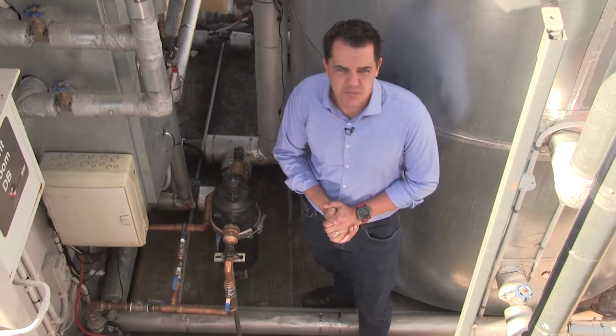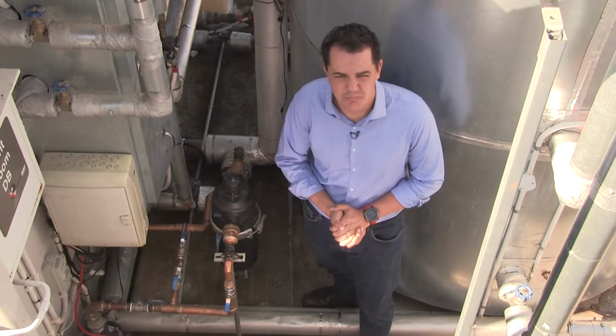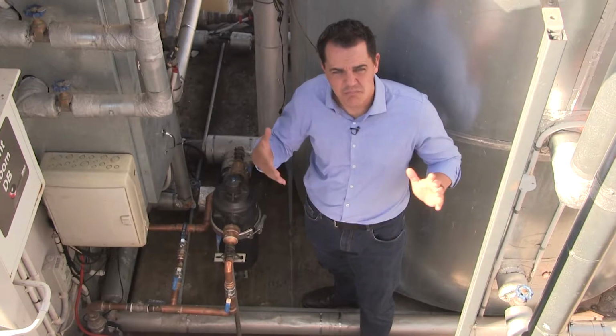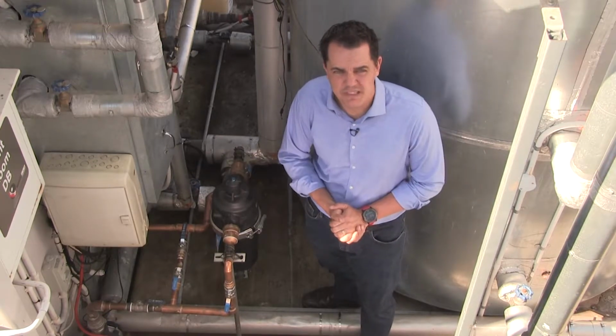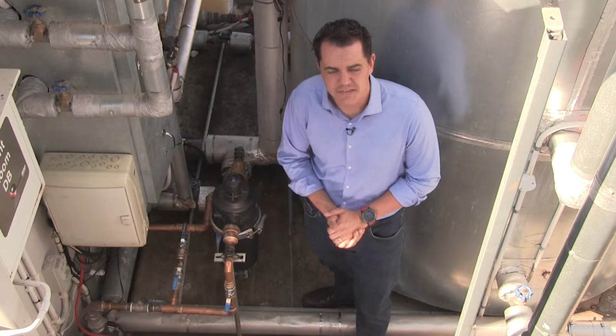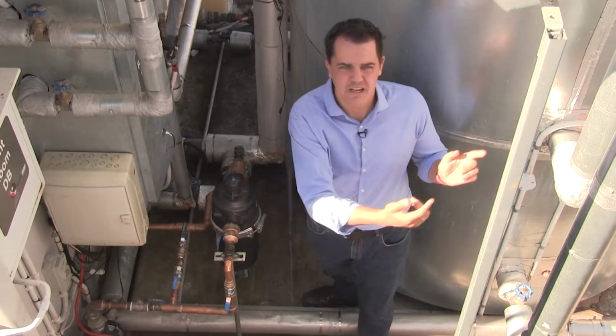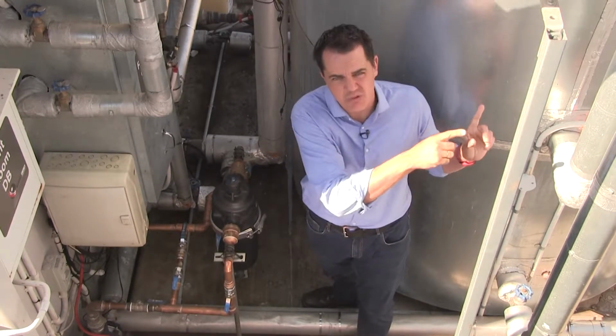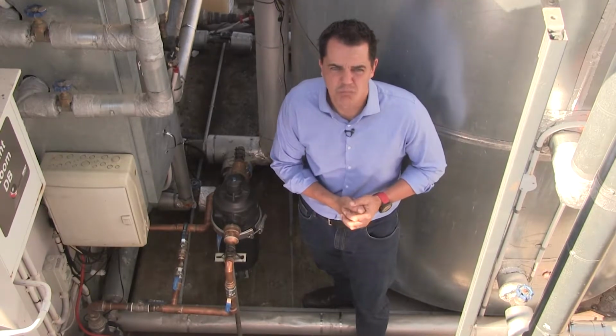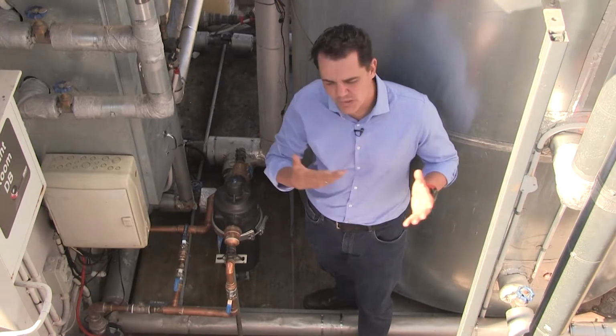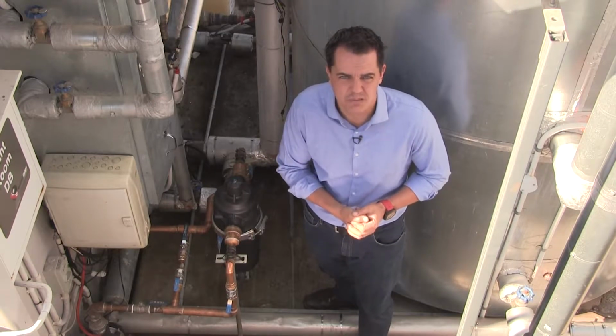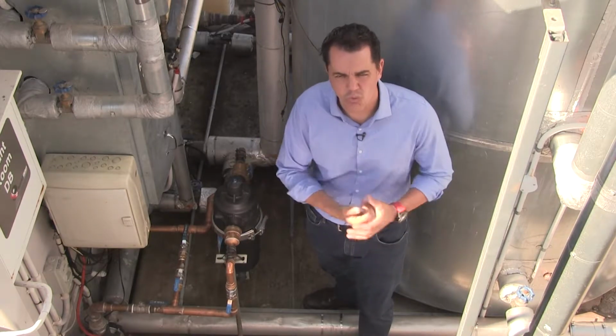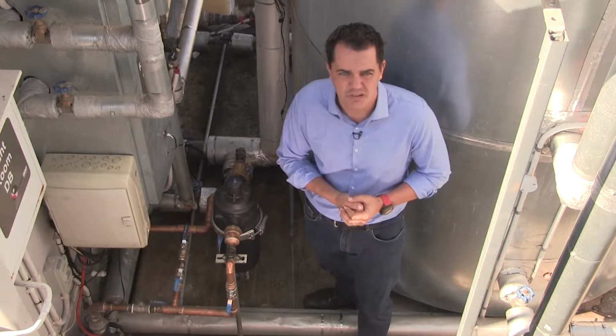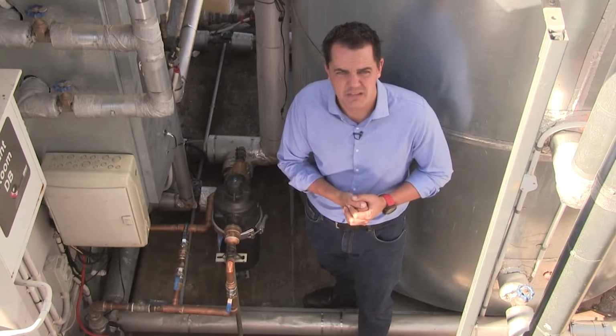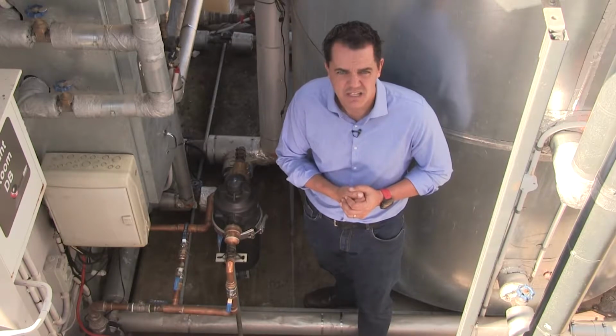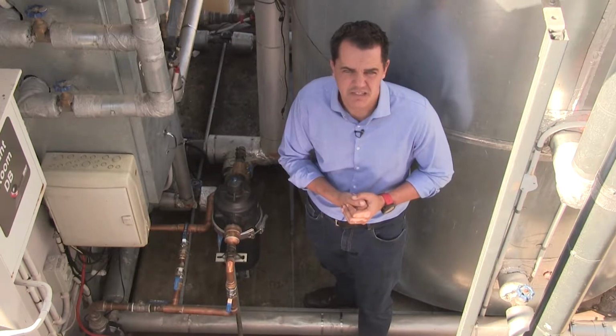We're at the Webster plant. This plant was designed by myself at Black Dot Energy and basically supplies the whole Webster building with hot water. Initially in this design, we had 49 electrical geysers placed within the shafts of these bathroom units. And when we built this extension on Webster, we basically replaced all those with gas burners out of this central plant. This video specifically is about the gas burners. So it's number 3 of the technical videos.